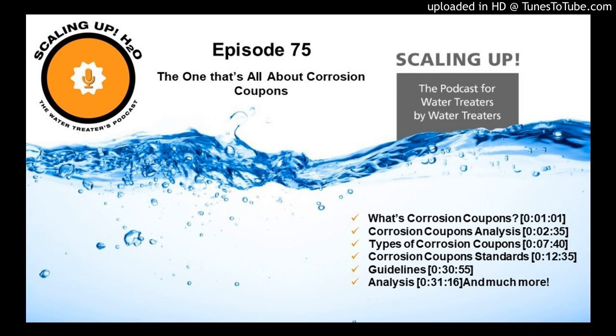And then we go ahead and write our reports. If it's a regular HVAC cooling tower or a process cooling tower, chiller, or closed loop system, something like that, the Association of Water Technologies has a standard guideline that they have put into the marketplace to say this is what is acceptable for mild steel and copper. I will make sure to have that on my show notes page so you can see exactly what that is. But I do want to explain a little bit about how the analysis works.